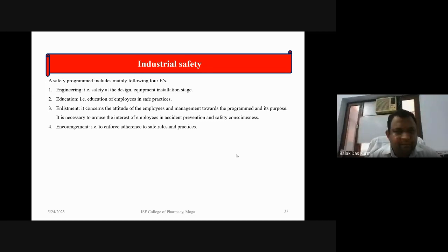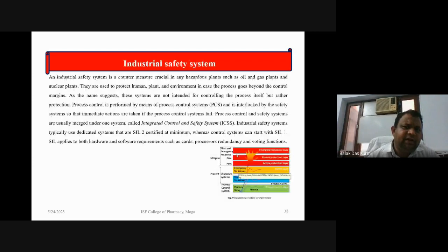safe rules and practices. So an industrial safety system is a countermeasure crucial in any hazardous plants such as oil and gas plants and nuclear plants. They are used to protect humans, plant, and environment in case the process goes beyond the controlled margin. As the name suggests, these systems are not intended for controlling the process itself, but rather for protection. Process control is performed by means of the process control system and is interlocked by the safety system so that immediate action is taken if the process control system fails.